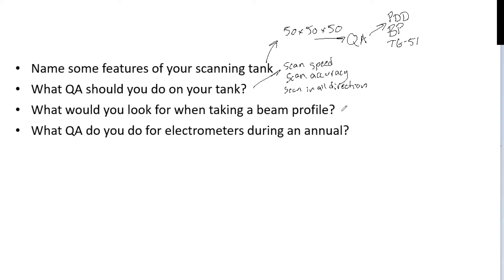So what would you look for when taking a beam profile? The first thing is speed. Most speeds are around 0.5 cm per second. However, if you do a slower speed, you get a smoother reading, you get better penumbra accuracy. If you're doing small fields, you want a really low speed. So something you need to consider.